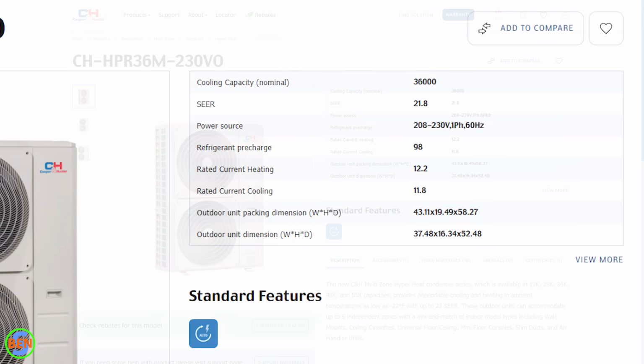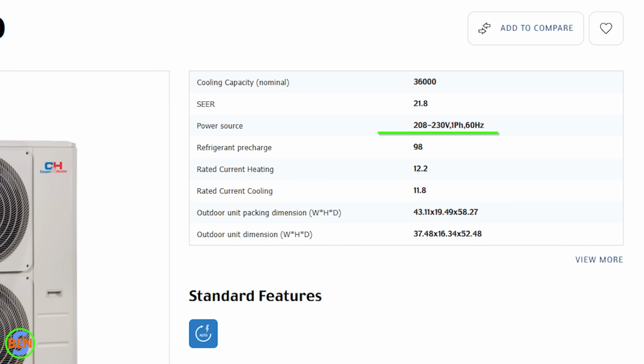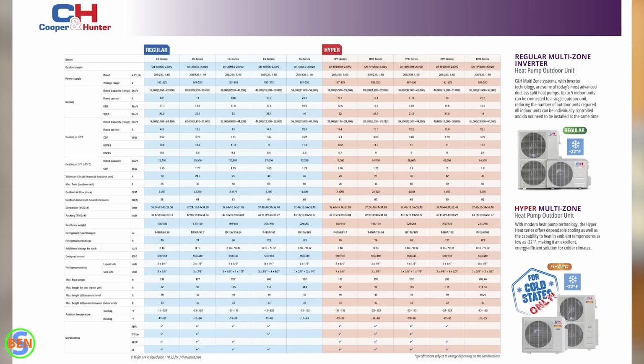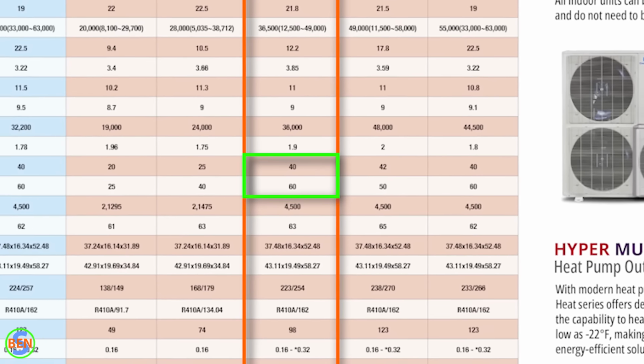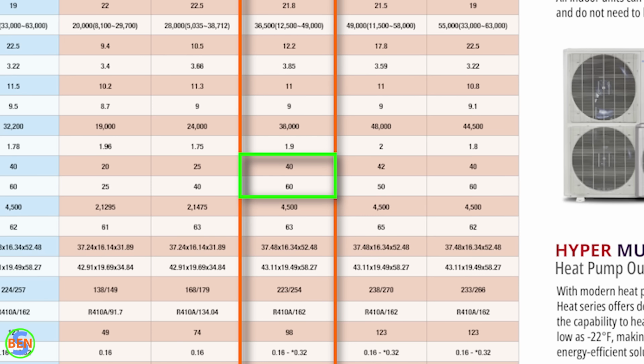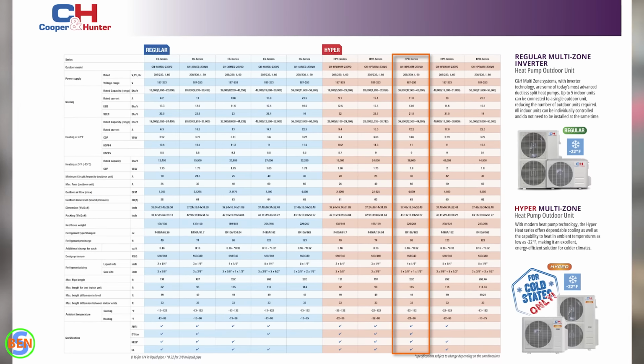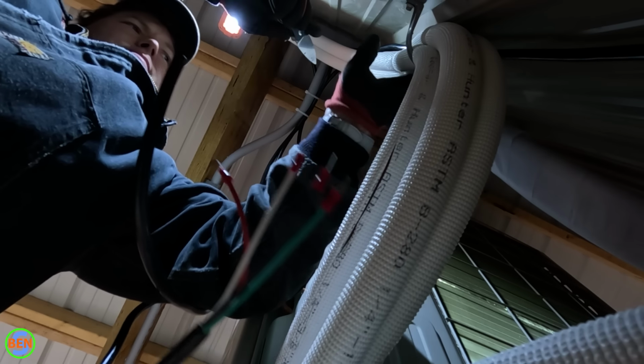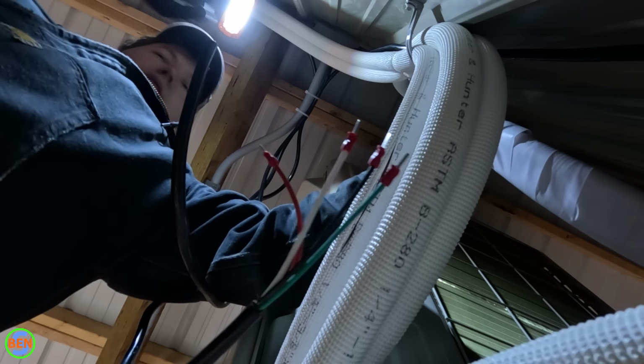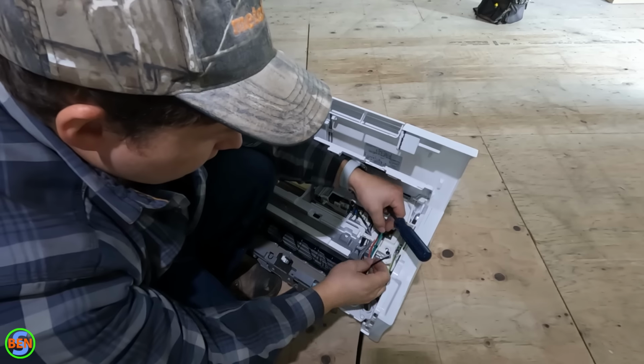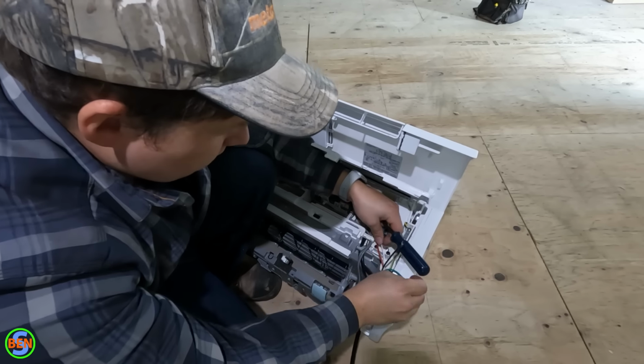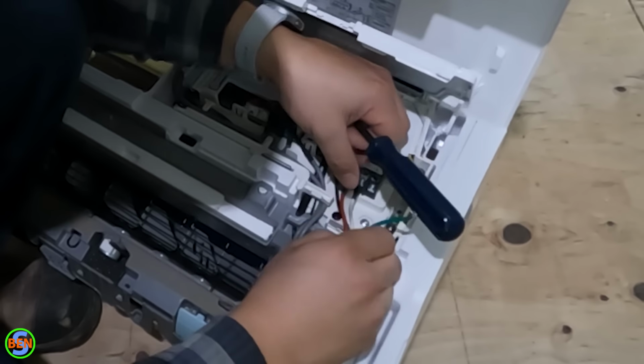The first of which is that most of these outdoor units are going to be 230 volts, or 208/230. Now, the size of the circuit that we ran to this particular one, the minimum is 40 amps, the maximum fuse or circuit breaker was 60 amps. So a 40 amp circuit at 240 volts should be adequate for this particular outdoor unit. That's pretty much the only thing you have to worry about when it comes to a main power source, because from here everything is distributed to the different units inside via a 4-conductor cable that is included with the line sets.